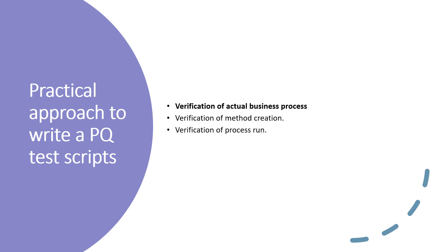Next is verification of process run — that means you are going to perform the test in the system. After creation of the instrument method, you need to create the sequence and processing method to execute the process of analysis. After completion of the run, you need to perform integration of the chromatogram, and there will be a report template by which you can generate the required results.